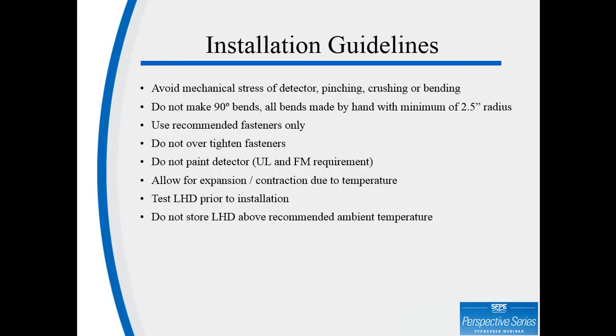LHD installation guidelines. Avoid mechanical stress of the detector: pinching, crushing, or bending. All of those operations should be done with the fingers and hands, not with any kind of tools. Do not make 90-degree bends. All bends should be made by hand with a minimum of a 2.5 inch radius. Use recommended fasteners only. Do not over-tighten fasteners. Do not paint the detector, a UL and an FM requirement. Allow for expansion and contraction due to temperature. The detector should be loose in the fitting. Test the LHD prior to installation as per manufacturer's instructions, and do not store the LHD above recommended ambient temperatures.